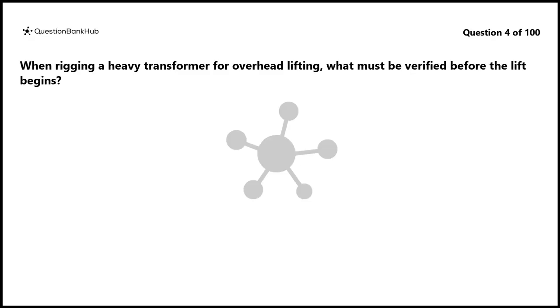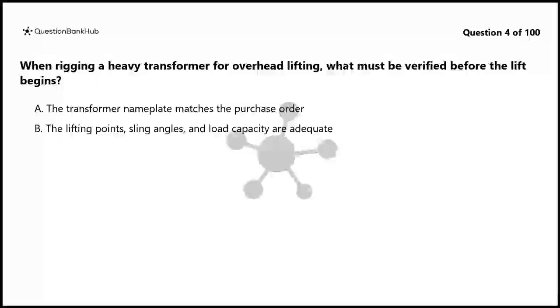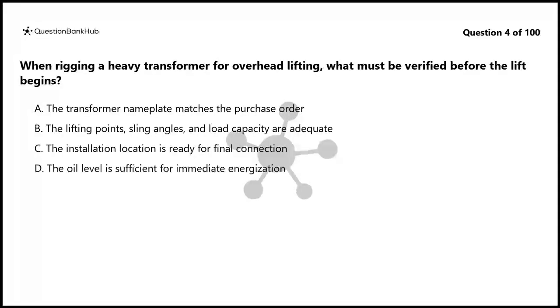Question 4. When rigging a heavy transformer for overhead lifting, what must be verified before the lift begins? A. The transformer nameplate matches the purchase order. B. The lifting points, sling angles, and load capacity are adequate. C. The installation location is ready for final connection. D. The oil level is sufficient for immediate energization.